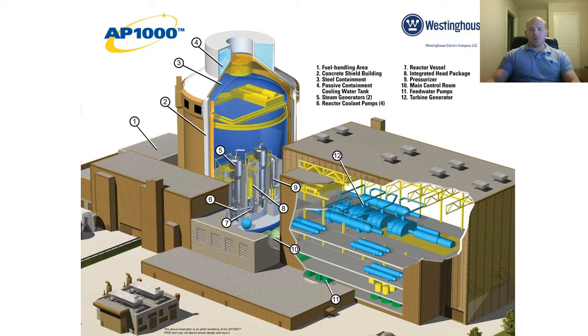It has 2 redundant 4 megawatt standby diesel generators that can power station service, all the system loads needed to run the place for a period of 7 days with no off-site support. And those 4 megawatt standby diesel generators are not required to cope with a station blackout. The water sources: you have the passive containment cooling water storage tank, as well as the passive containment cooling ancillary water storage tank. The passive containment cooling water storage tank can cool the containment shell for 72 hours, and then the ancillary tank can provide makeup water and extend that coverage for another 4 days, so a total of 7 days. That's just water stored on site.